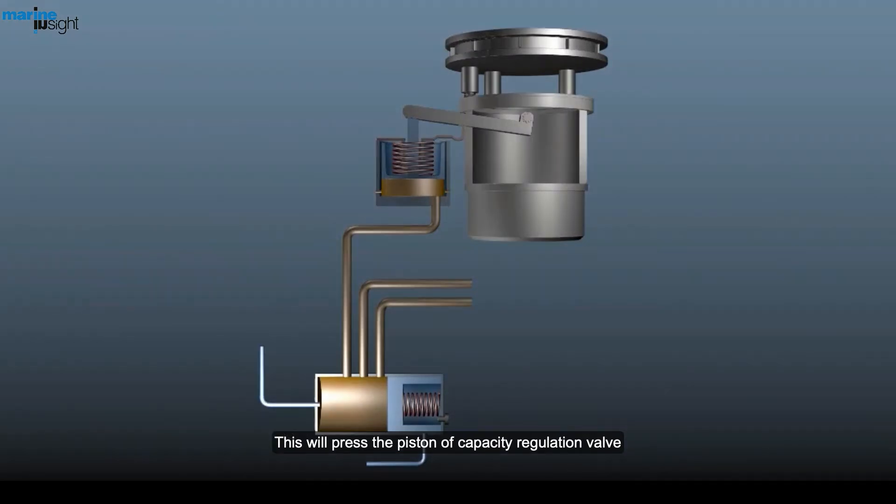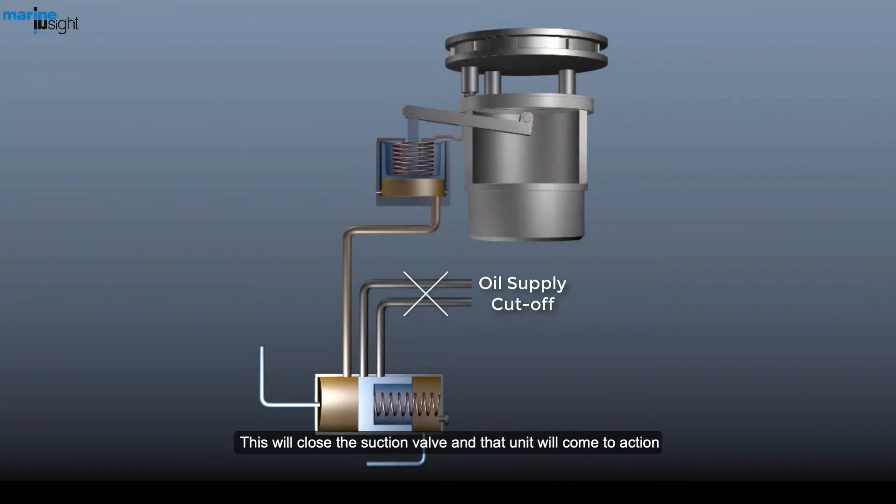This will press the piston of capacity regulation valve, cutting off oil supply and blocking the oil supply to unloader unit. This will close the suction valve and that unit will come to action.